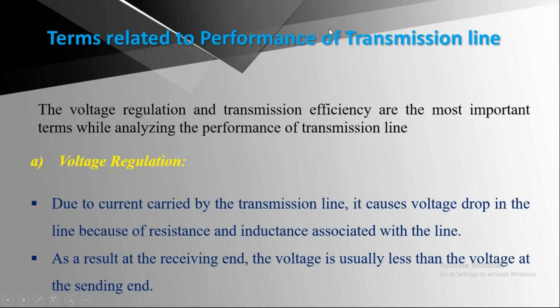So these terms are related to the performance of a transmission line. It means that if you want to analyze the performance of a transmission line, we have to find two parameters: voltage regulation and transmission efficiency. These two parameters are used to analyze how the transmission line will be performing. The voltage regulation formula is no load voltage minus full load voltage, divided by full load voltage, into 100. That is the formula for voltage regulation.